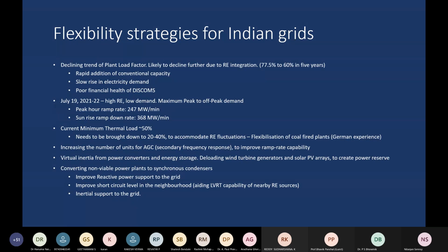Okay, great. So virtual inertia is when you have the power output of the wind turbine or the solar farm change as a result of the change in the network frequency. So deloading of the wind turbines and the solar photovoltaic arrays can give some virtual inertia, and this virtual inertia mimics the behavior of turbines, which are actually shafts, solid mechanical devices which are rotating at very high speed in the synchronous generators, the alternators, and they are locked to the grid frequency. So that is the physical inertia that is available, and we'll talk about that in more detail in a minute.